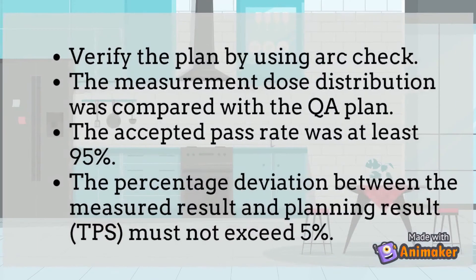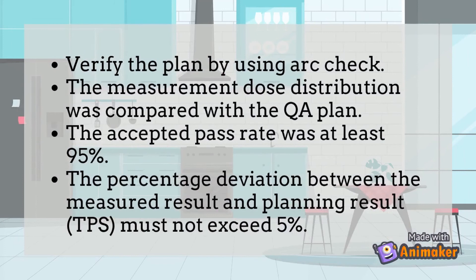The plan was verified using ArcCheck. The measured dose distribution was compared with the QA plan. The accepted pass rate was at least 95%, and the percentage deviation between the measured result and the planning result must not exceed 5%.